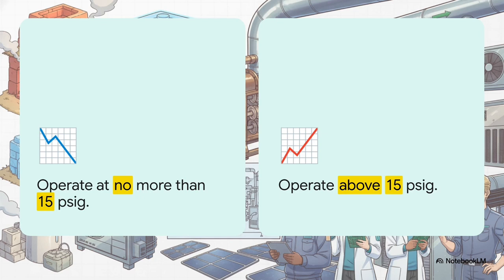You had low-pressure steam systems operating at no more than 15 psig, and high-pressure steam systems operating above that. But operating these required immense care. Think about this: when water boils into steam, it expands to about 1,600 times its original volume. Because steam has the capacity to expand at such high velocities in all directions, poor boiler operation could be a literal disaster. That's exactly why strict engineering codes had to be written, to manage this incredible force and basically stop things from blowing up.